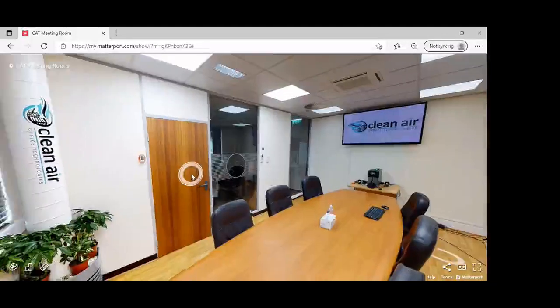There's a couple of elements to prove the facility is working. You've got a device here which monitors the airflow and plays a little animation to indicate that the air is flowing, to give confidence that the fans are operating. We've also got a magnehelic here that goes just outside the space, so you can see that it's slightly positively pressurised before going into the room. And at high level up here, you've got a test port. This is where a validation engineer would come around, inject aerosol behind the fan filter and measure the downstream concentration to make sure that the filter is integral and not letting anything by.